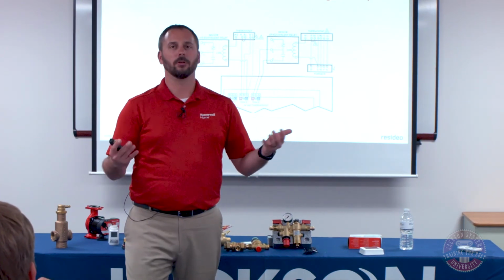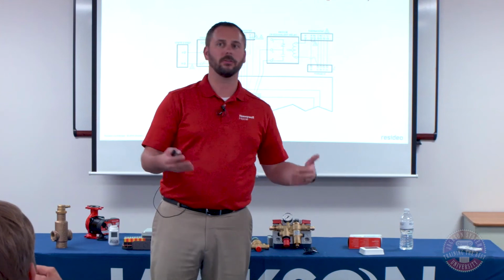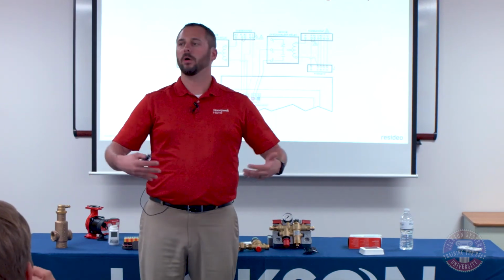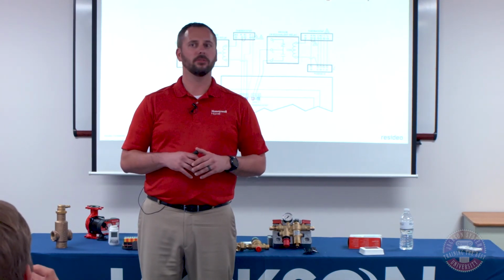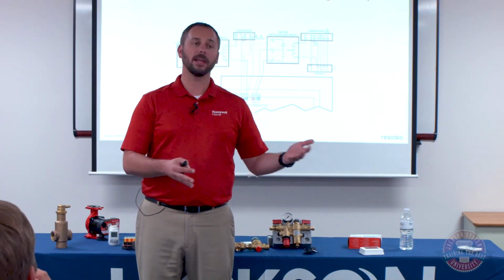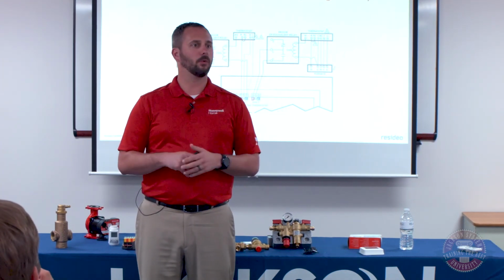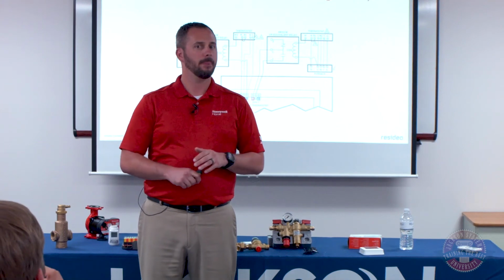They think there's a misconception they're always going to have warm floors, which is not always the case, but they at least want that radiant feeling. If you put in a standard 2-stage thermostat, we can make it work, but the forced air is going to come on way too often.